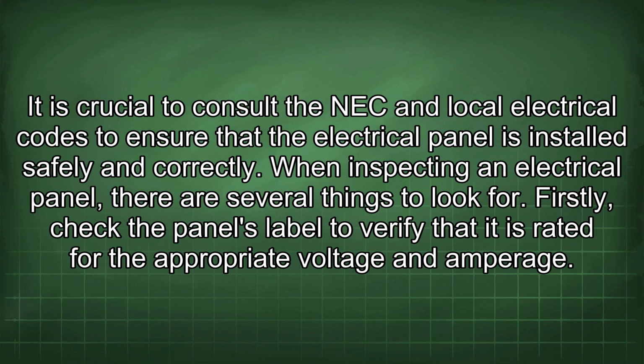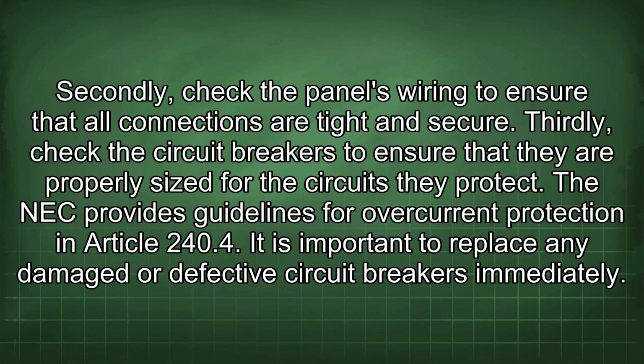Firstly, check the panel's label to verify that it is rated for the appropriate voltage and amperage. Secondly, check the panel's wiring to ensure that all connections are tight and secure. Thirdly, check the circuit breakers to ensure that they are properly sized for the circuits they protect. The NEC provides guidelines for overcurrent protection in Article 240.4. It is important to replace any damaged or defective circuit breakers immediately.